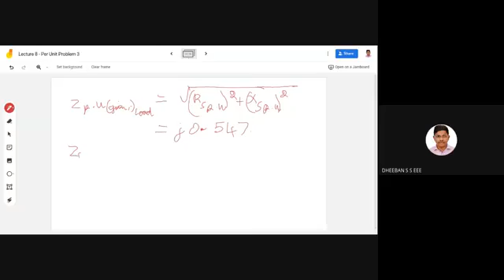After this, for the load, Z per unit new, we have to use the normal formula. It will be equal to 0.547 into 100, which is your base MVA, divided by the base MVA of the load which is 60, into 10.5 divided by 11 the whole square. So you'll be getting J equal to 0.831 per unit.